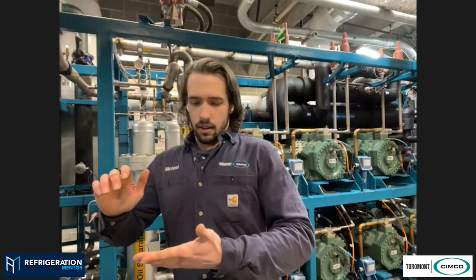With CO2, Benoit actually made this point the other day when he was here: you can get higher BTU capacity for heat recovery out of ammonia, but with CO2, because of the discharge temperatures we run, you can achieve higher temperatures for water heat reclamation. That's one thing I wanted to point out — that's amazing, one great thing about CO2. There are so many benefits and opportunities with its heat transfer properties.